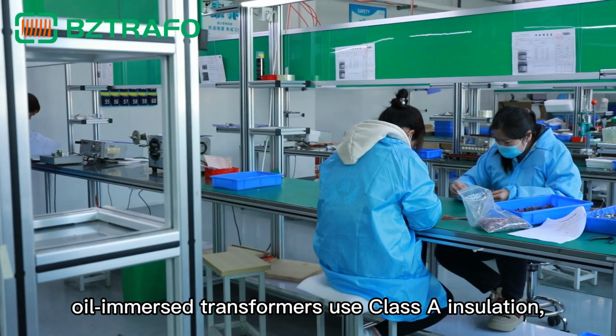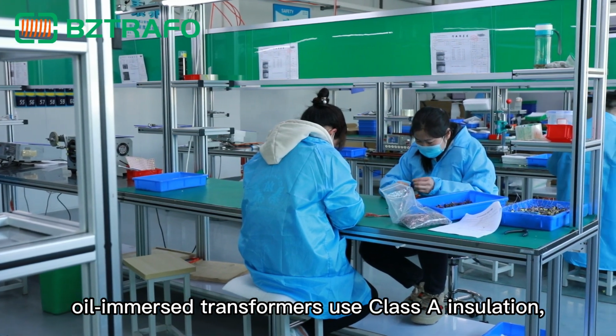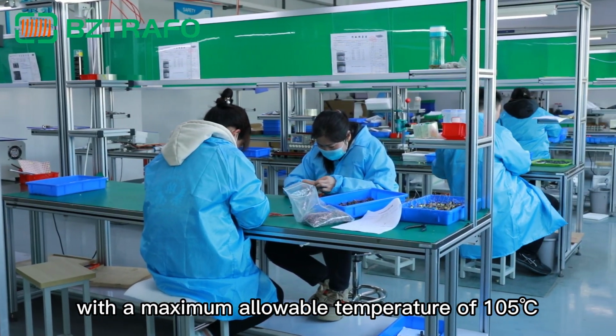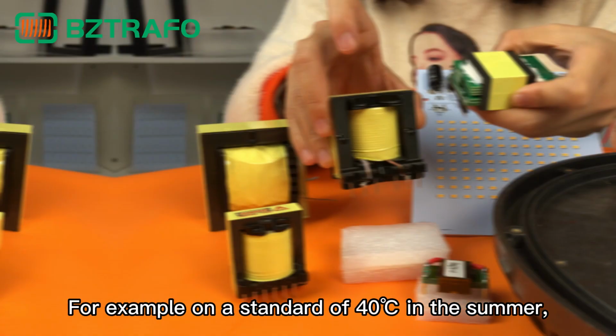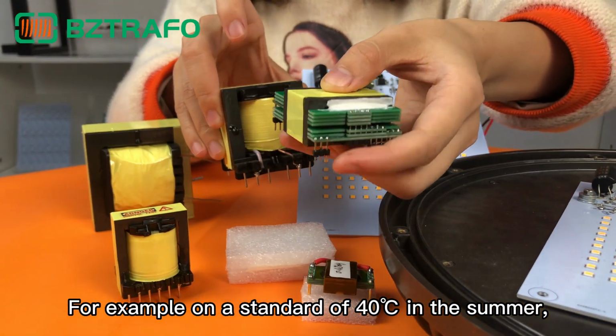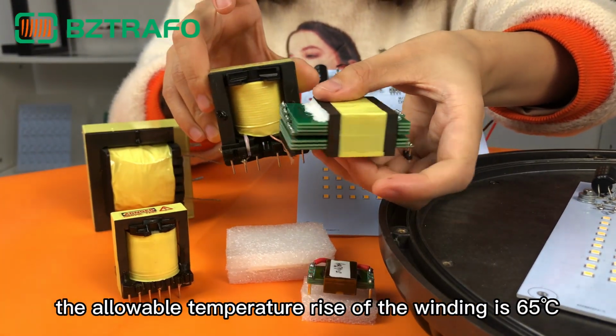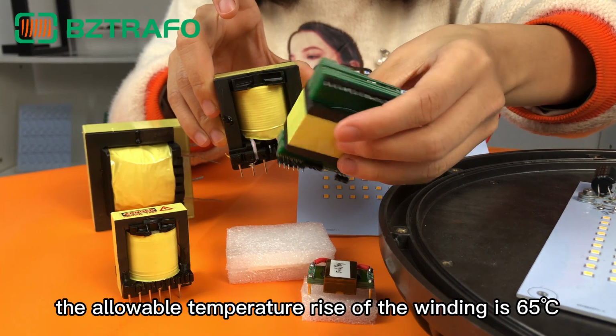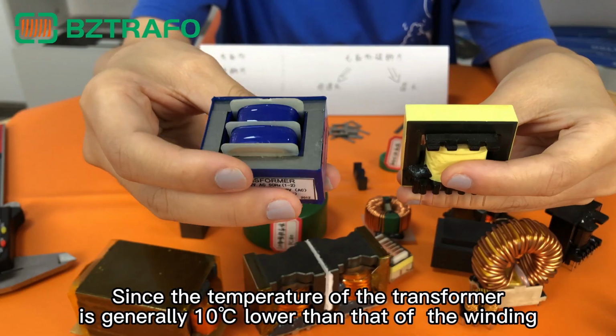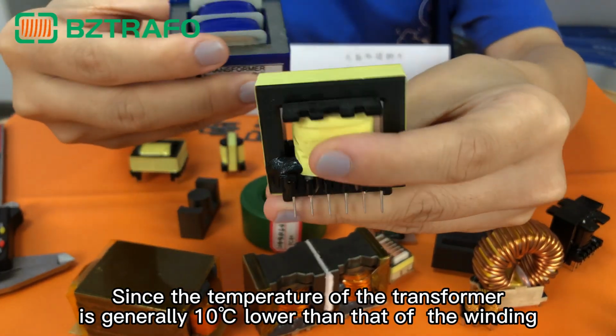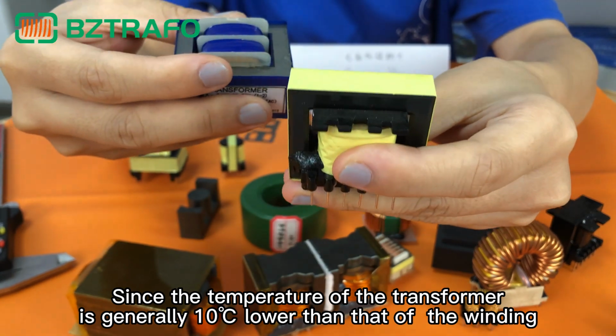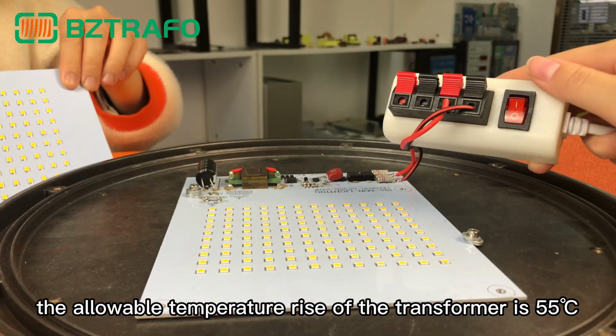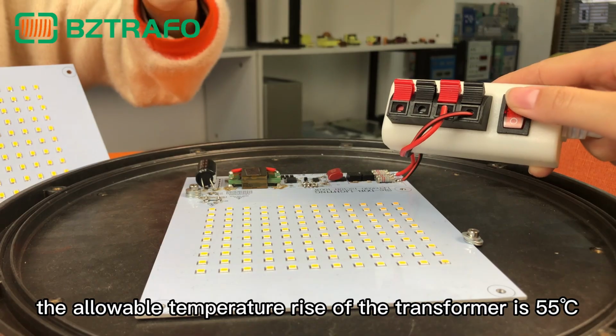Generally, oil-immersed transformers use class A insulation, with a maximum allowable temperature of 105 Celsius. For example, on a standard of 40 Celsius in the summer, the allowable temperature rise of the winding is 65 Celsius. Since the temperature of the transformer is generally 10 Celsius lower than that of the winding, the allowable temperature rise of the transformer is 55 Celsius.